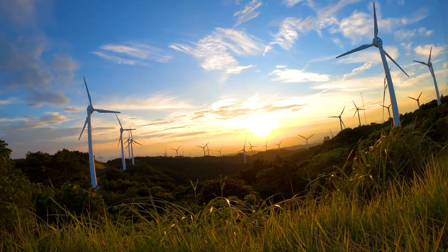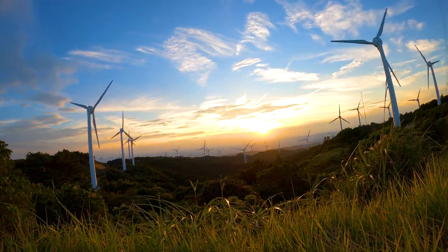But the benefits continue. Immersion cooling is much easier on the servers, and it also allows us to time-shift our cooling demand. During peak renewable generation times — when the sun is shining, the wind is blowing, and demand for electricity is low — excess fluid can be chilled, storing the cooled liquid for use during periods of high demand or when renewable energy production is low.